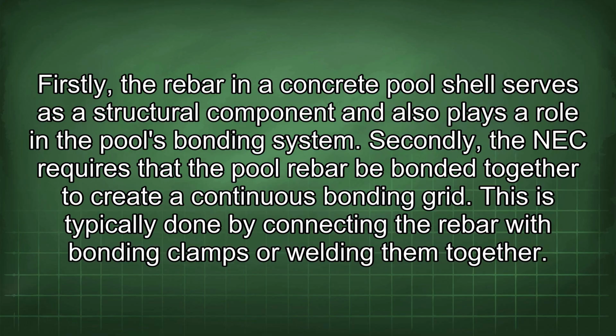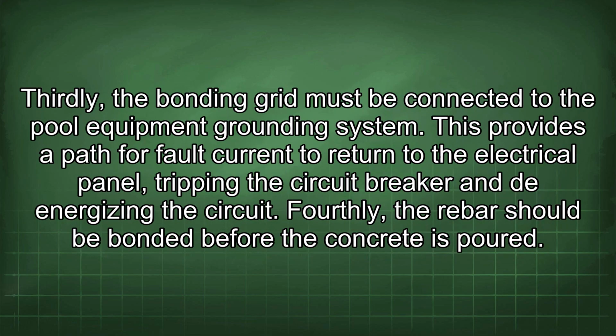This is typically done by connecting the rebar with bonding clamps or welding them together. Thirdly, the bonding grid must be connected to the pool equipment grounding system. This provides a path for fault current to return to the electrical panel, tripping the circuit breaker and de-energizing the circuit. Fourthly, the rebar should be bonded before the concrete is poured.